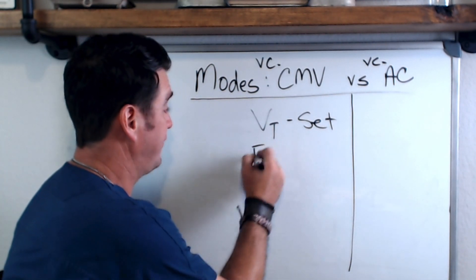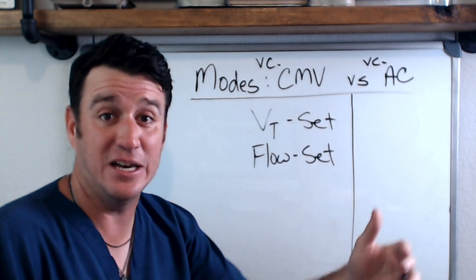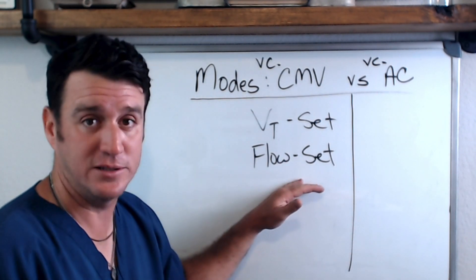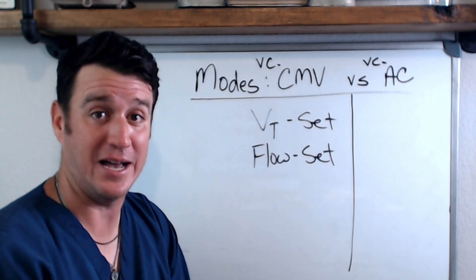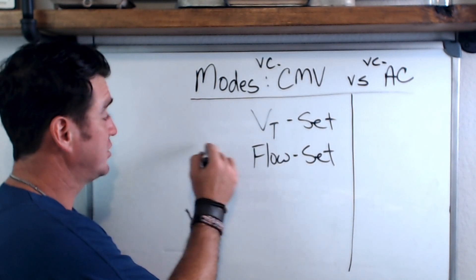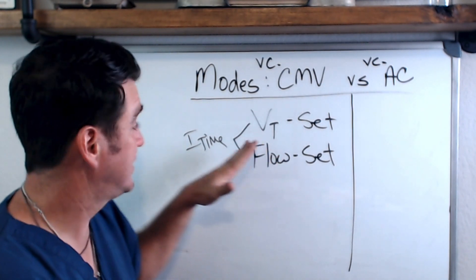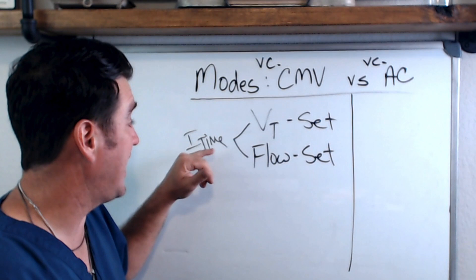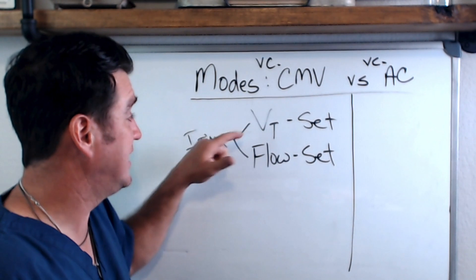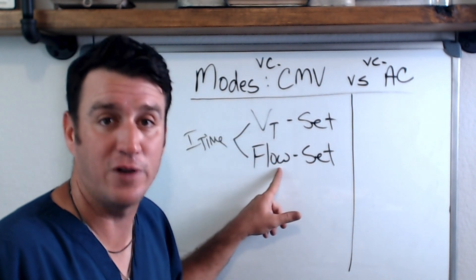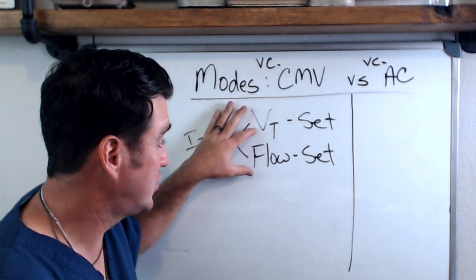We also tell the vent how fast to deliver that tidal volume — that's what flow does. If you set a higher flow, you deliver that tidal volume faster, which means a shorter I-time. Some vents have you set I-time instead of flow. Tidal volume and flow work together to establish a fixed I-time, and I-time is how long the inspiratory phase will last.